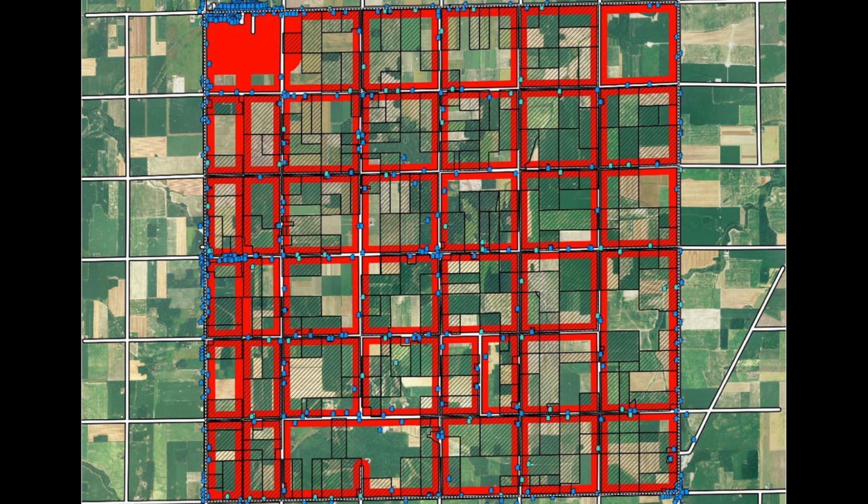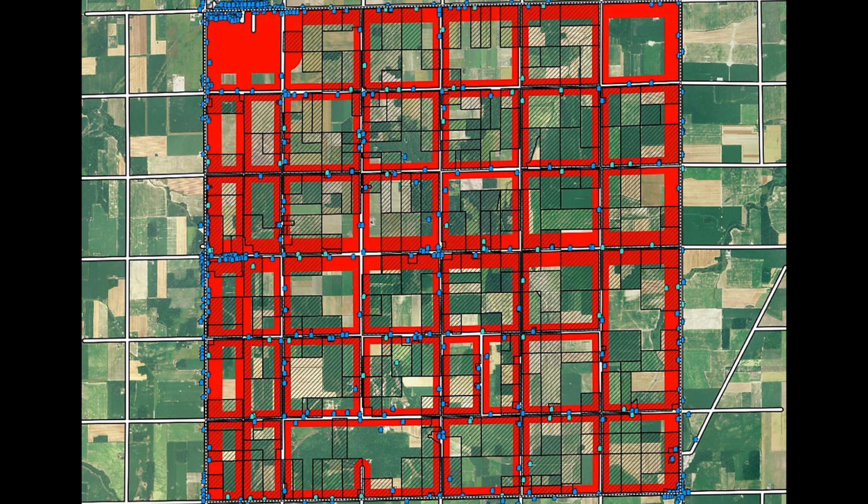We also have transportation setbacks. In this case, we're using 1.1 times the total turbine height, so the total height plus a little bit of margin, and we apply that to every public road and every other public right-of-way or private right-of-way that is of significance. So we have one railroad in this example, and then roads on almost every single mile. And so we use that total turbine height setback on roads. We also have in this project about 4 roads that are paved in this region that are also very heavy traffic. So we apply an additional margin, about doubling the base setback on those heavy use areas.